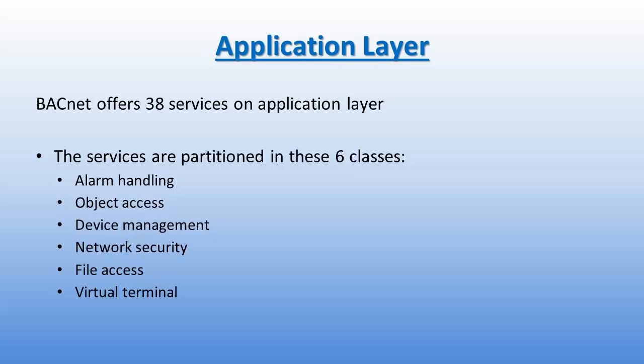At the application layer, BACnet uses objects and services to complete all its tasks. BACnet offers over 38 services. These services are partitioned into six classes: alarm handling, object access, device management, network security, file access, and virtual terminal. Some examples of these services would be read, write, change of value notification, and time synchronization.